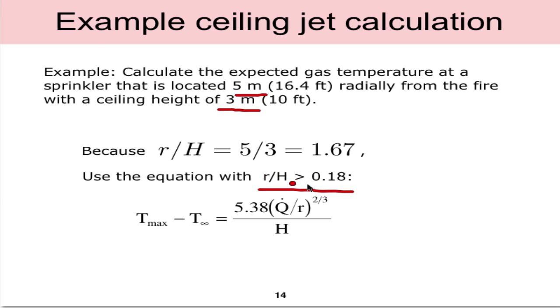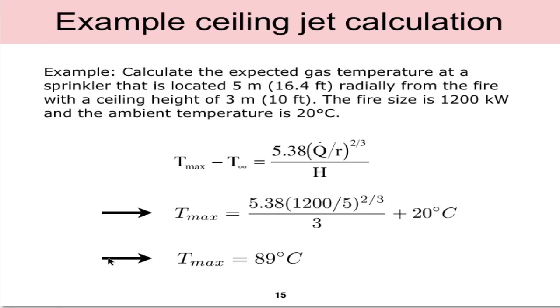If we plug in the values to that equation you can use a spreadsheet for this. In order to calculate the temperatures we need to know the fire size and the ambient temperature, so I've given those as 1.2 megawatts or 1200 kilowatts and an ambient temperature of 20 degrees celsius. If we plug in 1200 kilowatts, five meters radially r, and h equal to three...